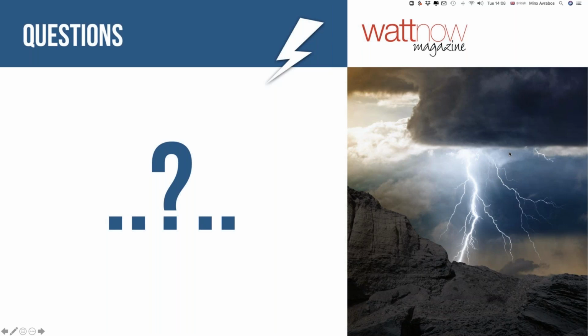Now, don't forget that if you go to IEC 62305, you'll find they talk about two lightning protection earthing systems: type A and type B, where the length or dimensions of the electrodes are specified according to the level of protection and the soil resistivity. They say that if these criteria cannot be followed for any reasonable reason, then they can achieve a limiting earth resistance of 10 ohms. That is the IEC standard value.